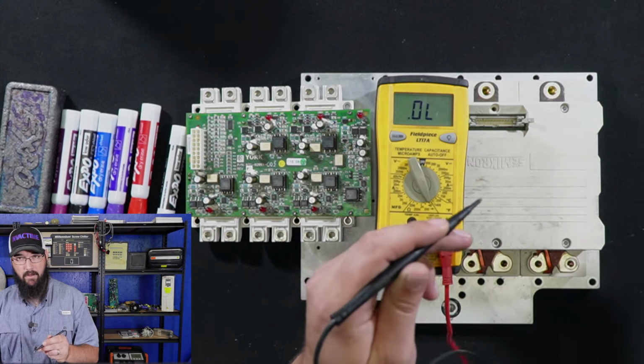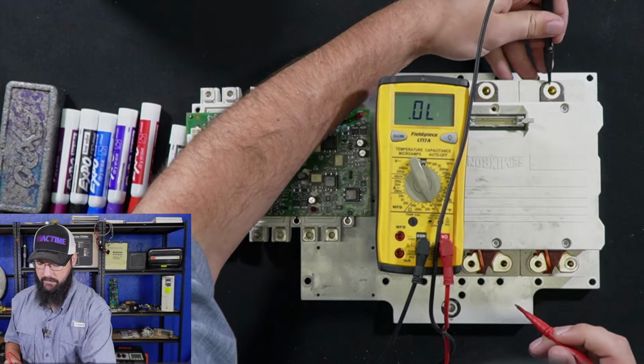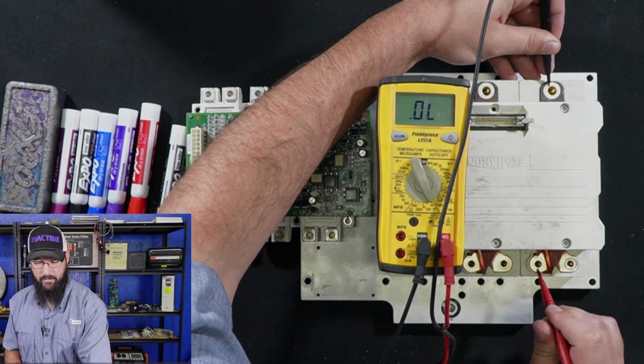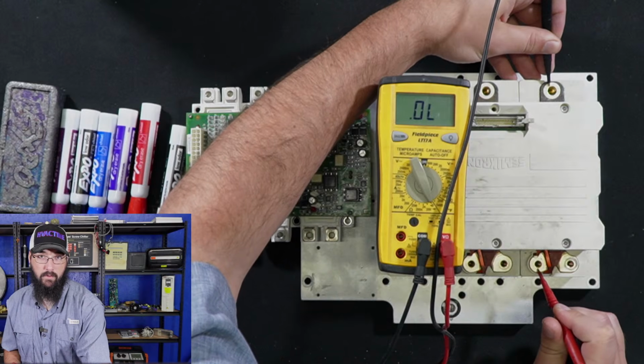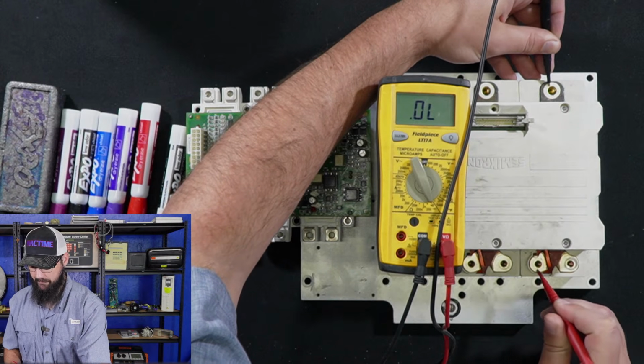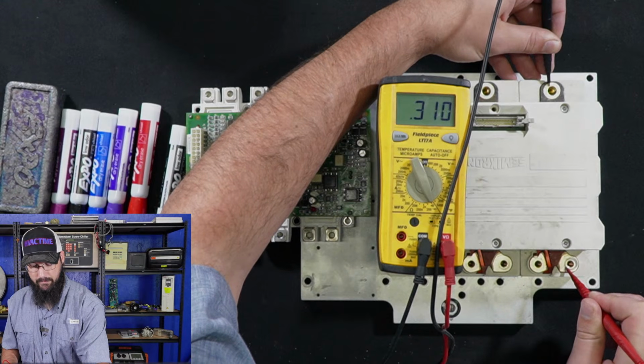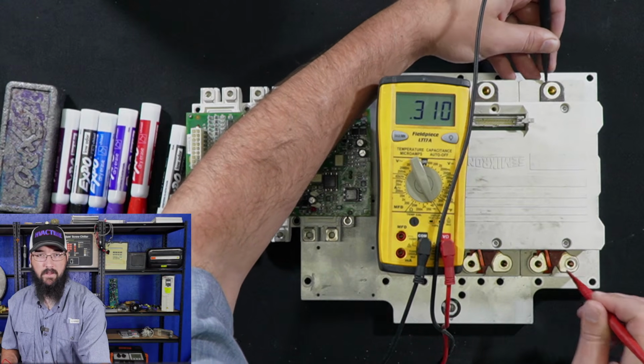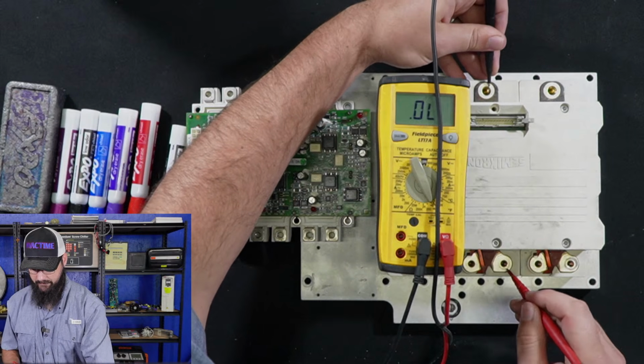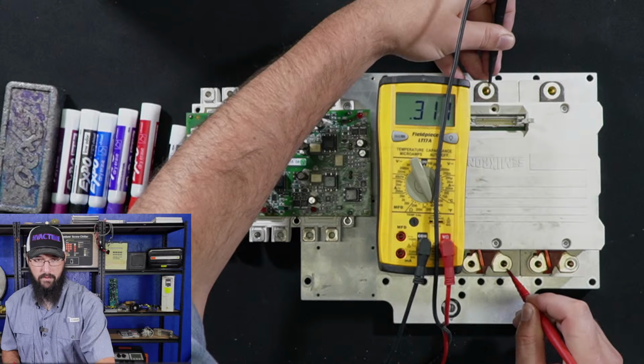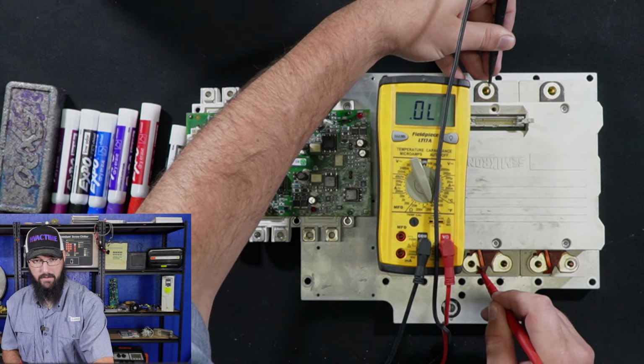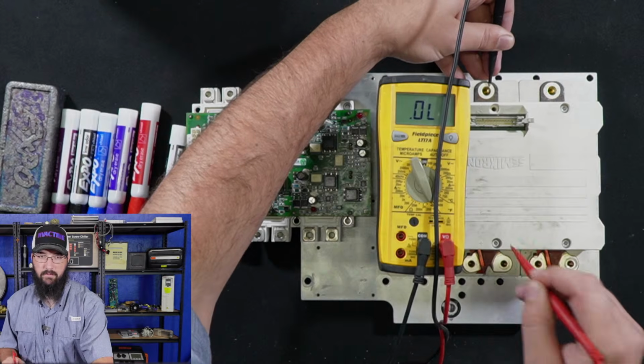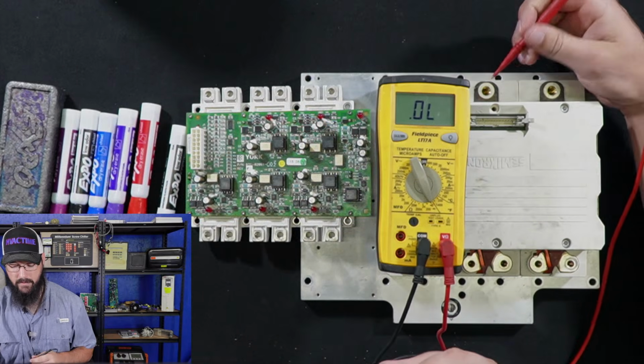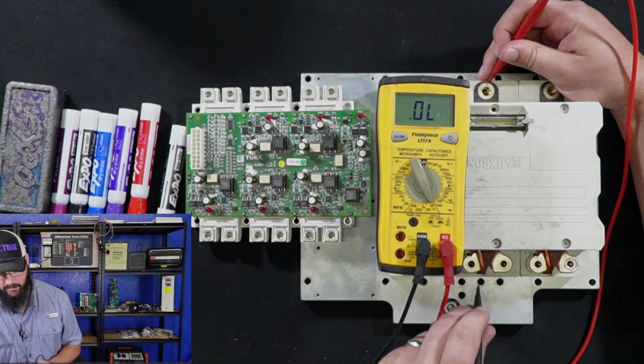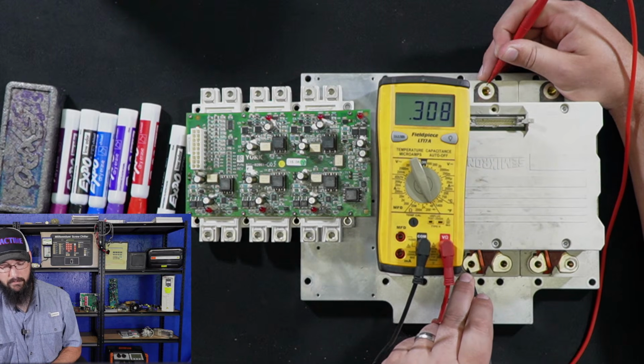Now I'm going to flip my leads. Negative lead goes on the output, on my inputs. Earlier I had 0.31, now I have OL. I go to the negative input and I have 0.31. Let's switch to the next leg. We have 0.31 and nothing. I went negative to positive that time, so I didn't follow the exact same sequence. Hopefully you're able to track. I'm going to go positive lead to the output, negative to the positive input. We'll round that to 0.31. It's close enough.